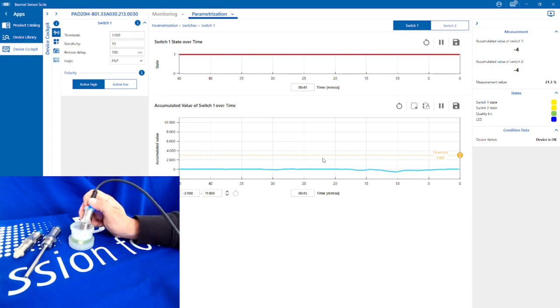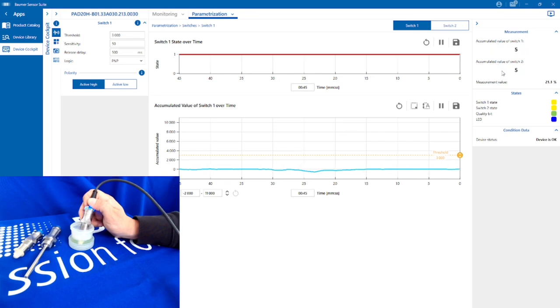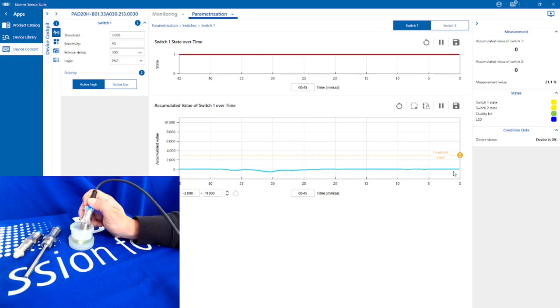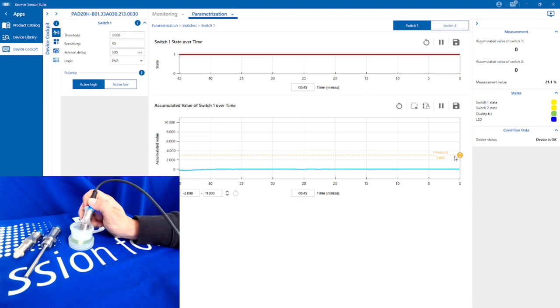From the software here, the sensor is showing me at the moment switch one, and I've got an accumulated value. This is the actual reading of the output of the sensor and it's reading around about zero, plus or minus twenty, hovering around that level pretty steady. This is exactly what you do in your application: you install the sensor and monitor where your accumulated value would be, and then you can add a threshold to switch when the sensor's seeing a certain amount of air.